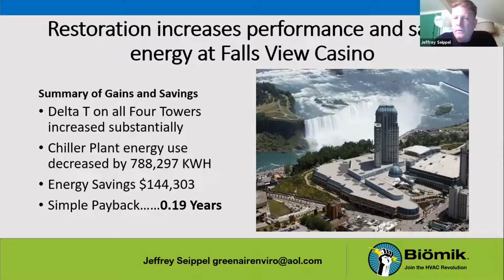The chiller plant used almost 800,000 kilowatts less that year than it did the previous year. And the energy savings were about $144,000. That's in Canadian dollars. The simple payback for that project was not even a couple of months. So it's very immediate and very beneficial to optimize these structures. It has an immediate impact on the performance and overall system efficiency.